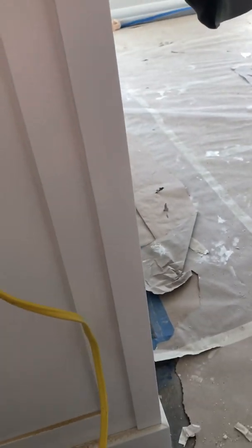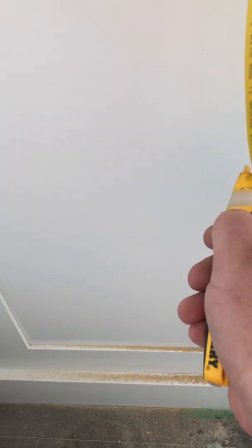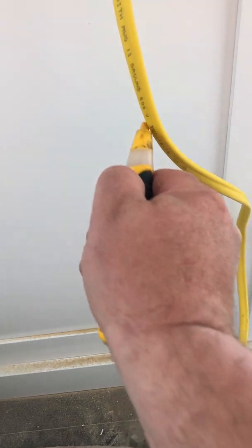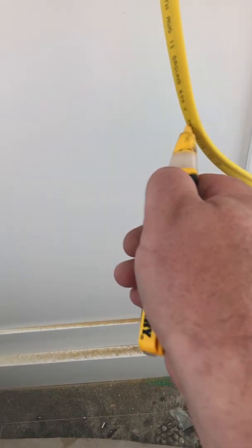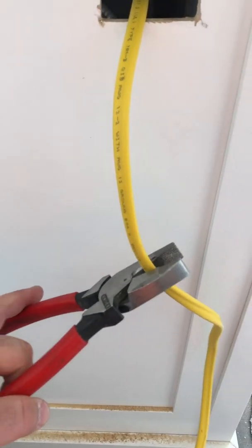I pull this wire and leave a little bit of slack in there because in case somebody else has to work on it again another day, they'll have some wire to play with. We turned the power off yesterday, so I want to make sure the power is still off with this power tester — which it is. So I can go ahead and cut the wire.